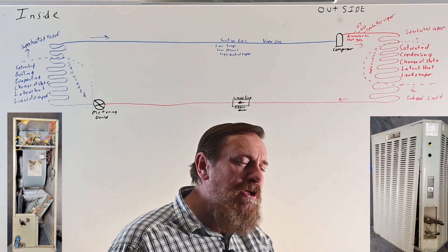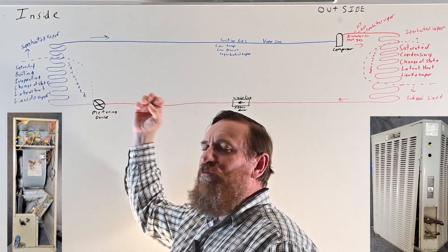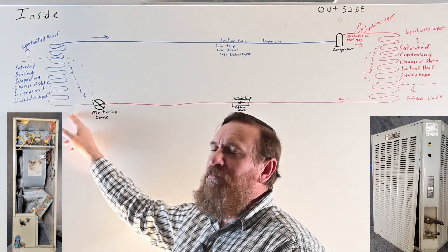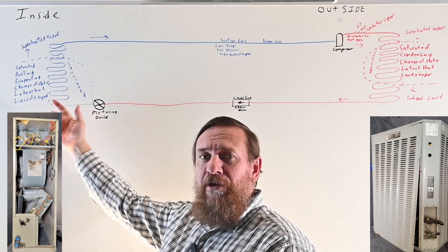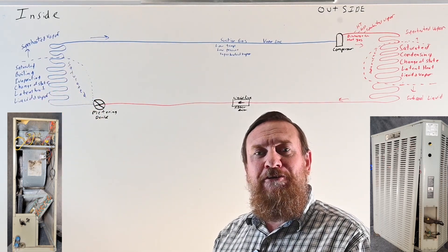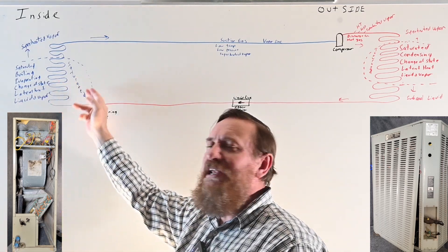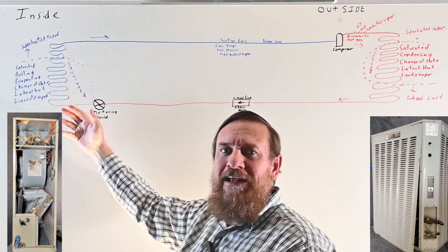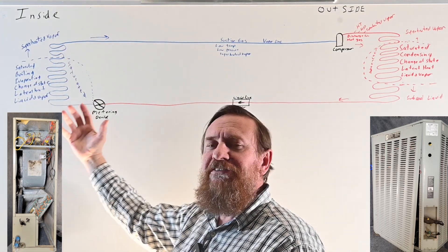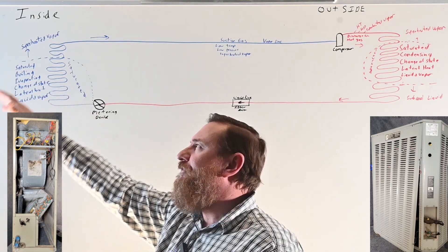You touch the line and it's a warm sub-cooled liquid. From there we travel through our liquid line filter dryer and hit our metering device. That metering device reduces the pressure, which drops the boiling temperature, so the refrigerant can boil at a very low temperature. As it boils and changes state, it absorbs heat. The heat from the air in the house makes the refrigerant boil, and that refrigerant boiling absorbs heat from the air, so we're literally absorbing heat from the cooler indoor air and putting it into the refrigerant.